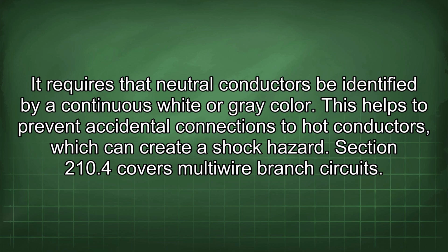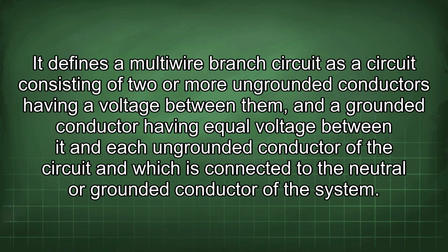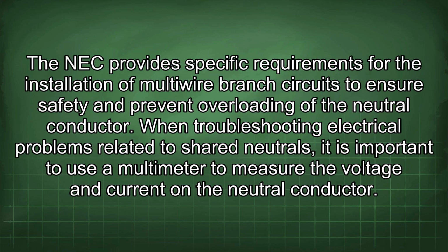Section 210.4 covers multi-wire branch circuits. It defines a multi-wire branch circuit as a circuit consisting of two or more ungrounded conductors having a voltage between them, and a grounded conductor having equal voltage between it and each ungrounded conductor of the circuit and which is connected to the neutral or grounded conductor of the system. The NEC provides specific requirements for the installation of multi-wire branch circuits to ensure safety and prevent overloading of the neutral conductor.